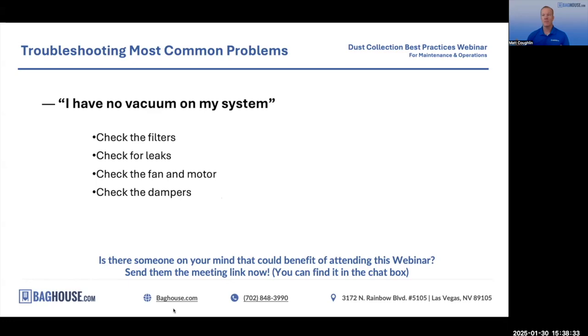Over time, maybe you have reached that end of life failure where your filters are now blinded, your filter cleaning system isn't working like you want it to, and so the result is a static pressure that's higher than your design point and minimized suction where you need it. So number one, we'll check the DP gauge. How are your filters doing? If necessary, we can do a visual inspection of the filters. They're totally packed with dust. There's your problem. New filters, problem solved, right? That's the best case, right? Easiest thing to figure out.